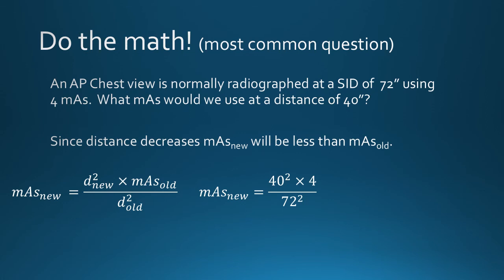Here is the equation written, and solving for the new MAS with the numbers substituted for the variables gives an answer of 1.24 MAS, which is smaller than 4 MAS. This compensates for the increase in radiation intensity seen at a shorter source-to-image distance.